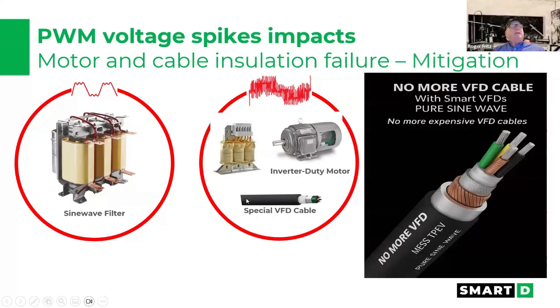over time. So the issues over here are, motors, they've got to be inverter duty. They've got to have typically grounding rings in. You put in specialized VFDs, you put in line reactors on the input, and you put sine wave filters on the output to clean all this up. Whereas if you use the actual Smart D control, on the outputs, you don't need specialized VFD cable anymore.